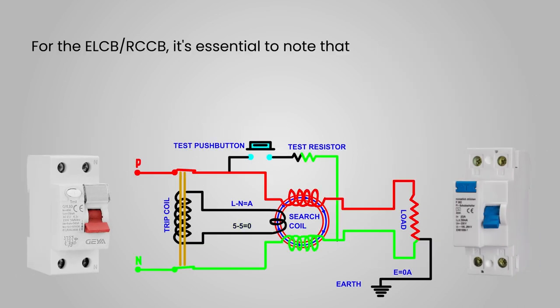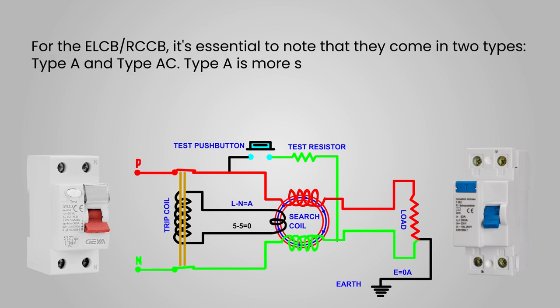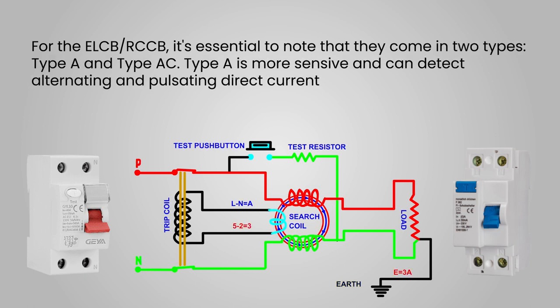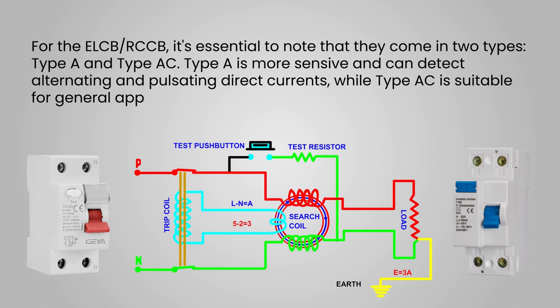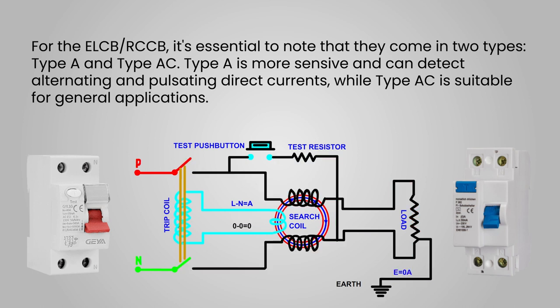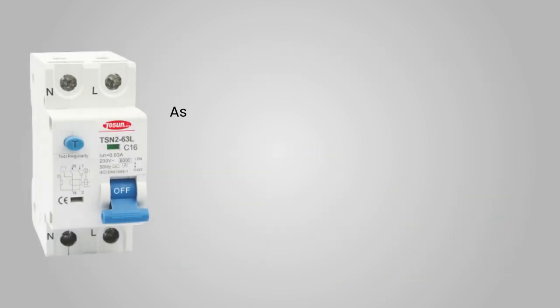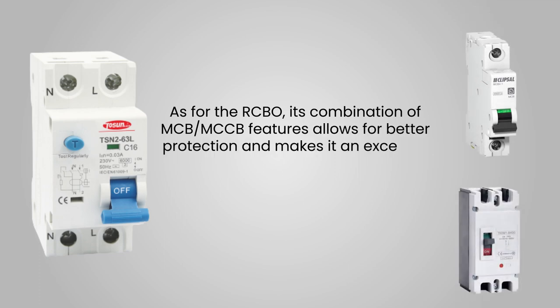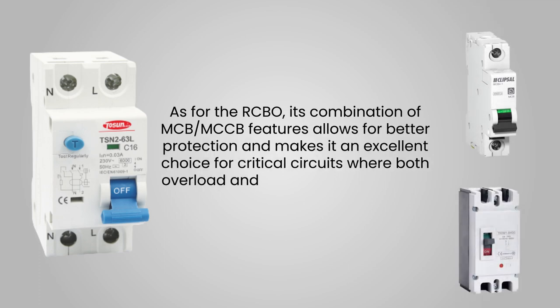For the ELCB-RCCB, it's essential to note that they come in two types: type A and type AC. Type A is more sensitive and can detect alternating and pulsating direct currents, while type AC is suitable for general applications. As for the RCBO, its combination of MCB and RCCB features allows for better protection and makes it an excellent choice for critical circuits where both overload and leakage protection are crucial.